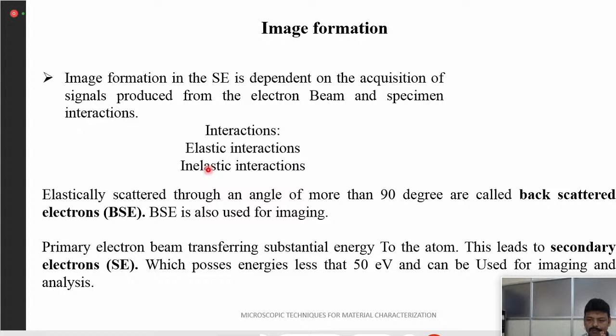You can see the image of the detectors for our system itself, the Hitachi SU6600. You can see the detector part. Different detectors are attached. We have 3 different kinds of detectors. We use the secondary electron detector for regular imaging. For some samples where we want to know the compositional difference in the image itself, we go for BSE imaging, backscatter electron imaging. And for X-ray analysis, when we want to know the elements present in the sample, we go for EDS analysis. The bigger blue one is the EDS detector. We'll be installing a new EDS detector to our system very soon.